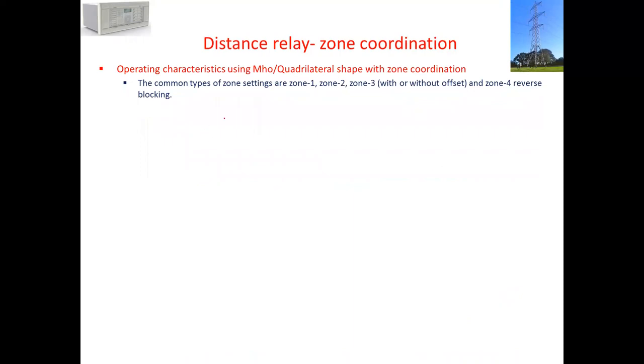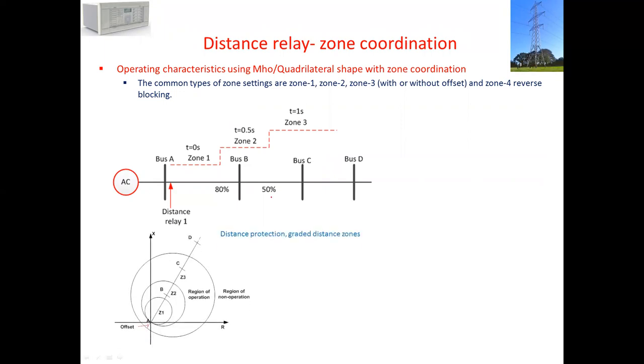The common types of zone settings are zone 1, zone 2, zone 3, and zone 4. If you look at the single line diagram, we have a relay and three zones. Zone 1 has a trip time of 0 second, zone 2 is 0.5 second, and zone 3 is 1 second. Zone 1 is at 80% of the line and zone 2 is at 50% of the next line. We'll discuss later in more detail why we choose these settings.